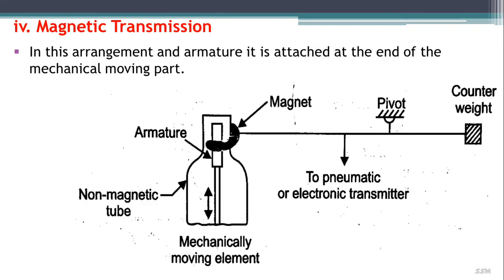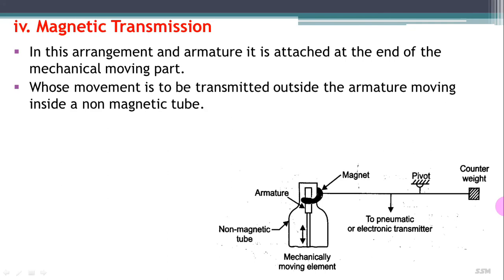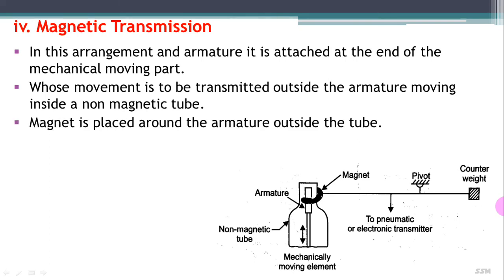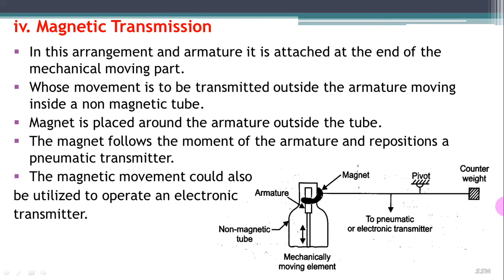Next is magnetic transmission. The arrangement contains an armature and a non-magnetic tube within which a mechanical movement element is attached, and the magnet arrangement is connected to a counterweight and a pneumatic or electric transmitter. An armature is attached at the end of the mechanical moving part whose movement is to be transmitted, inside the non-magnetic tube. A magnet placed around the armature outside the tube follows the movement of the armature and repositions a pneumatic transmitter. The magnet movement could also be utilized to operate an electronic transmitter.